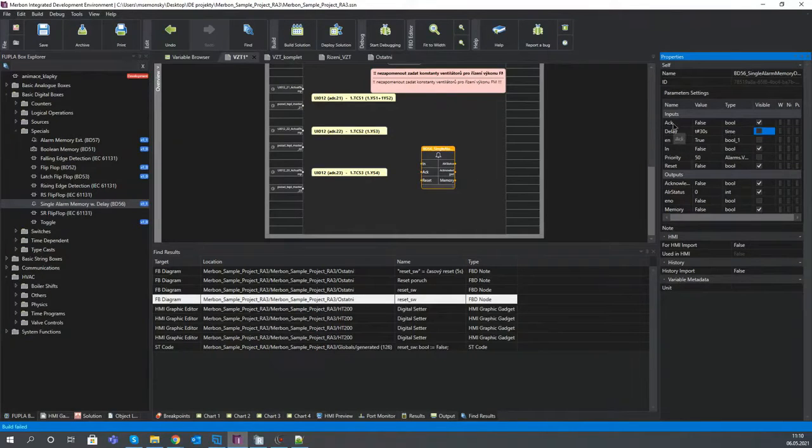Then the acknowledge and reset pins, they are necessary only in case you have a manual acknowledge and reset of alarms, like a button on a switchboard. Because normally, you can have two ways how to acknowledge and reset an alarm. Either you do it through an HMI, like SCADA or display on the controller, or web interface, terminal, HT200, or whatever.